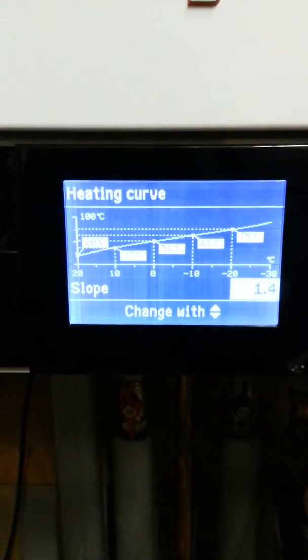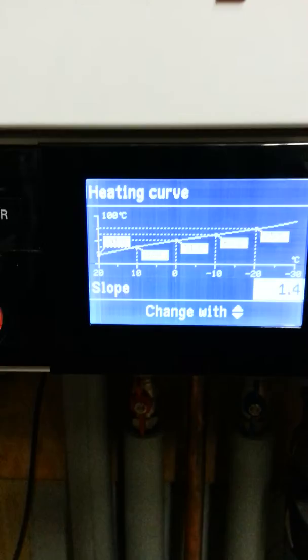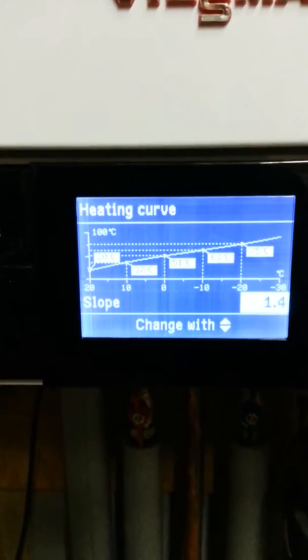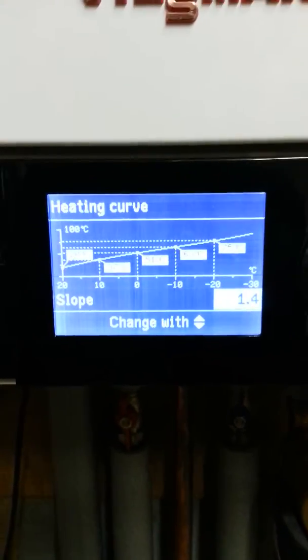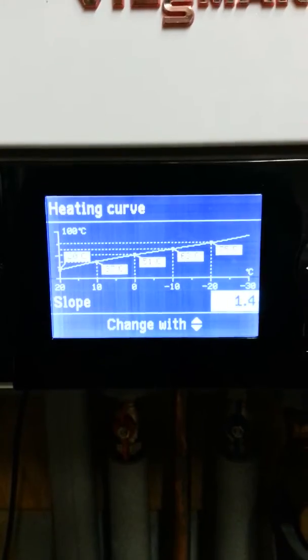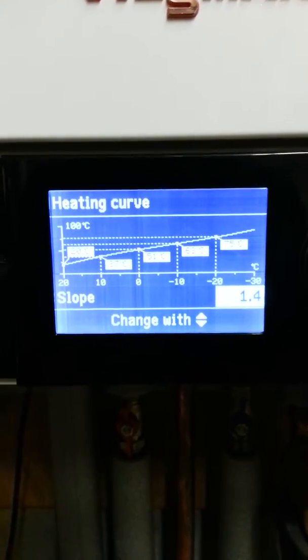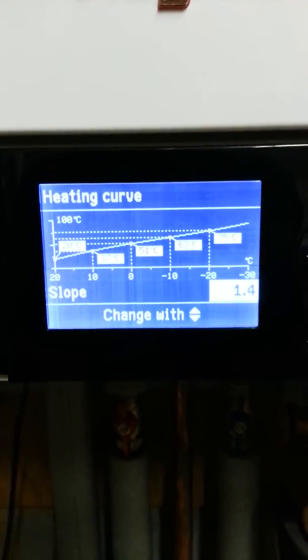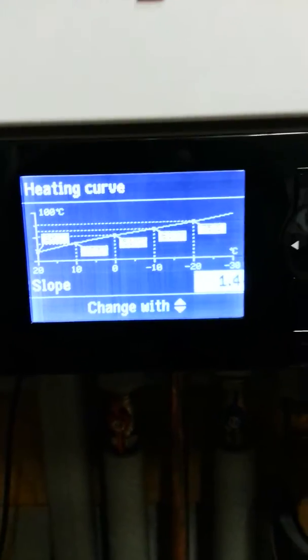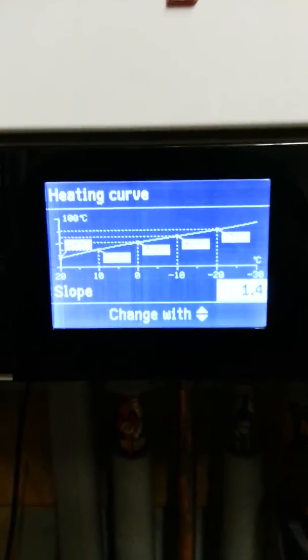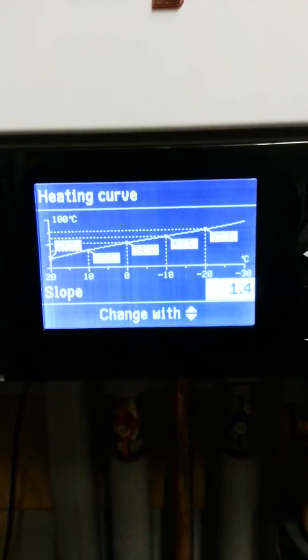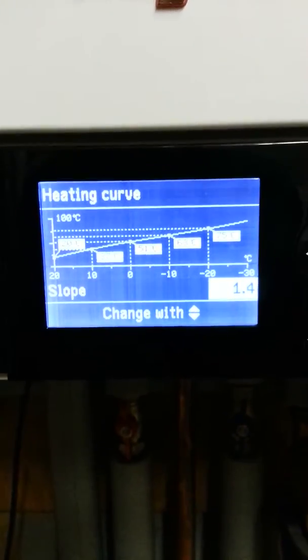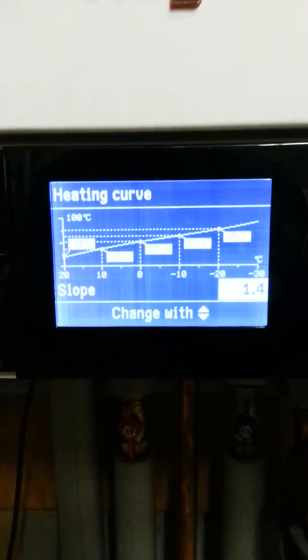So on this one, flow temperature to radiators at zero outside is 51 degrees centigrade. As I've talked about in previous posts, really not going to go out of condensing mode at any time unless you get to probably about start to cut condensing about minus five, which doesn't really happen in London very often.